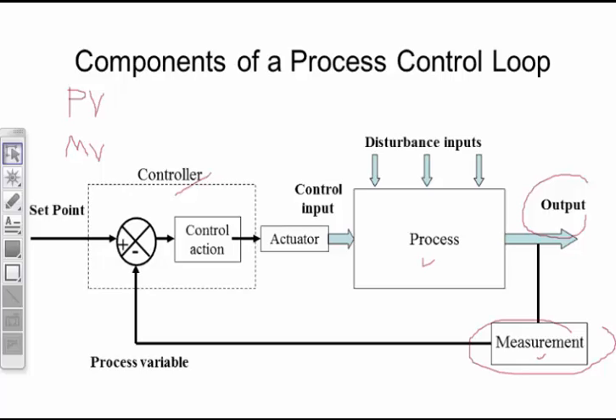The PV can also be an input to a data display, so the operator can use the reading to adjust the process through manual control and supervision. The variable which needs to be manipulated in order to have control over the process variable is called the manipulated variable or MV. If we control a specific flow, for instance, then we manipulate a valve to control the flow — the valve position is the manipulated variable and the flow becomes the process variable. In a simple automatic controller, the controller output signal OP drives the manipulated variable. In more complex systems, the controller output signal can drive the target or reference values for other controllers.